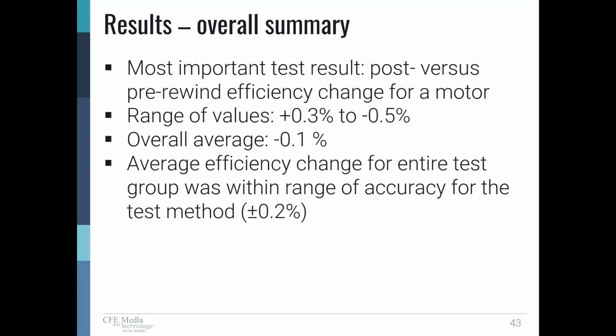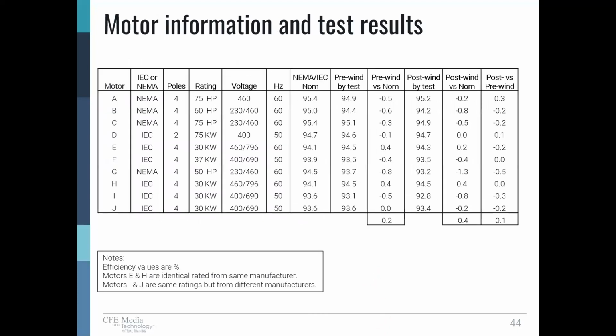So the most important test result, let's call it the bottom line, is the post-rewind efficiency versus the pre-rewind efficiency. What was the change? The range of values: one motor was as high as a 0.3% efficiency gain. Another motor at the low end of the spectrum was a 0.5% reduction in efficiency. Very narrow band, very small change in losses. The overall change out of the 10 motors was an average of 0.1%, which in itself is within that test method range of 0.2%. So really overall, very, very small change.